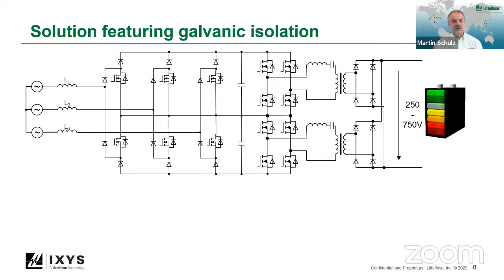It became a widely spread one because it offers power factor correcting strategies, as well as limited control over the DC voltage. So the DC link voltage can be controlled to be higher than the rectified one, which at least gives you some control. Galvanic isolation stages are very typically LLC stages because those provide the highest efficiency, and efficiency really matters in infrastructure systems. Power output of each unit tends to be in the 60 kilowatt, potentially even 100 kilowatt range.